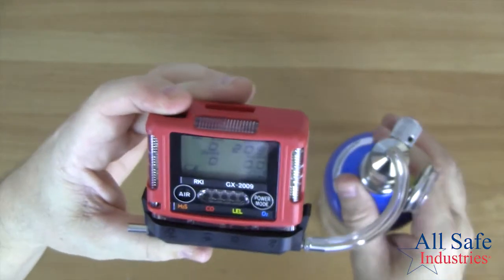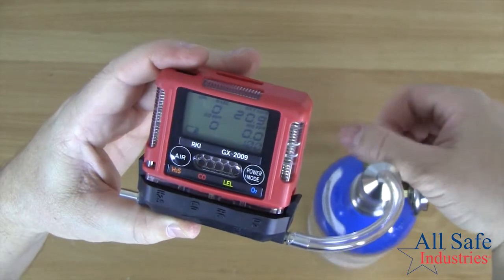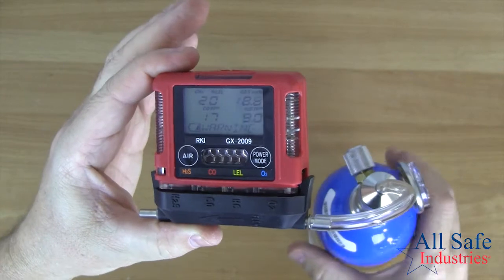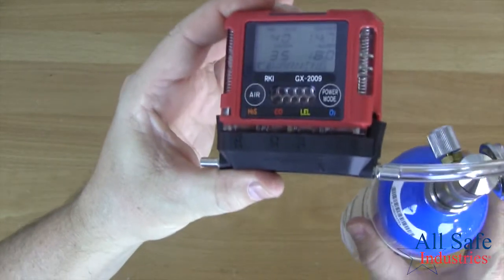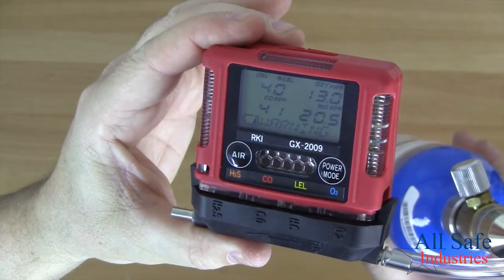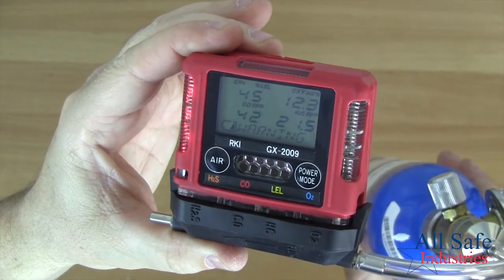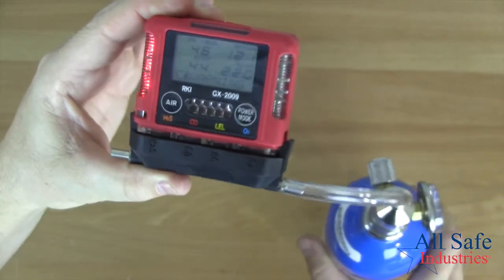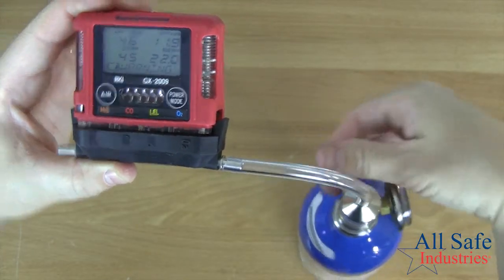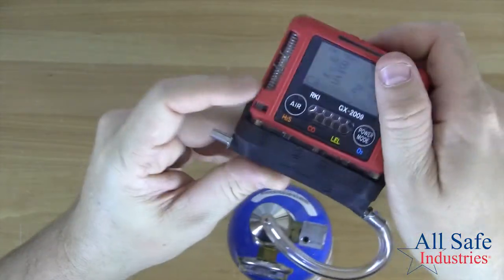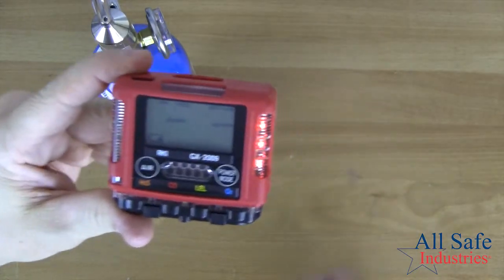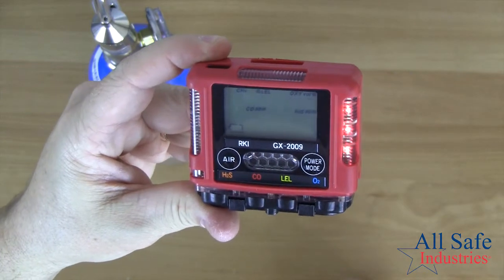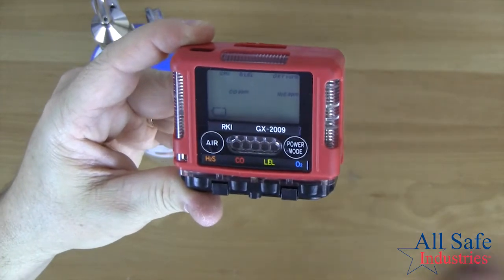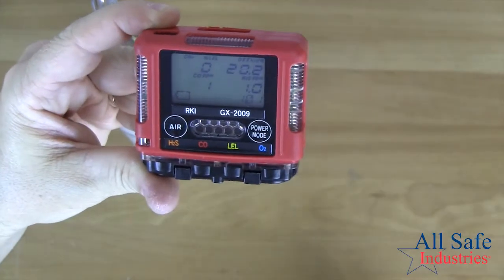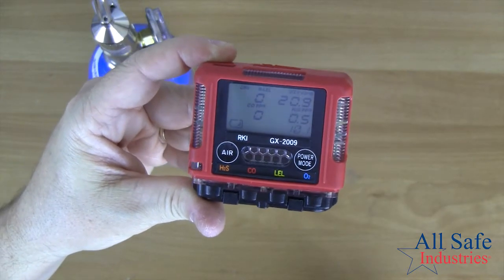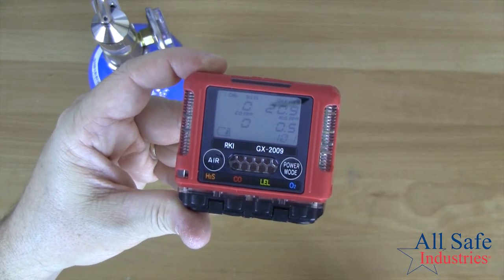So now we're ready to do our bump test, and it's really just as easy as turning on the gas. So I'm going to turn the gas on here, and then you'll hear the instrument go into alarm. It only takes a few seconds to do this test. If it takes any longer than 30 seconds, you should stop and calibrate. Once the gas concentrations come back down, you'll be able to hit the reset button. And that will silence the alarms. You won't be able to silence the alarms if there's a gas alarm. So if it's registering gas is present, it's going to stay in alarm.